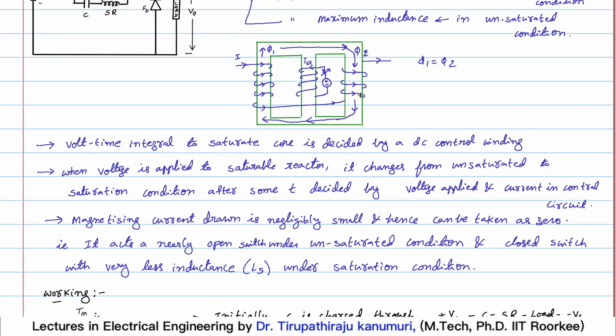The basic characteristic of this saturable reactor is that the voltage-time integral - that is, voltage multiplied by time duration - is fixed and decided by the current passing in the control circuit, mainly the DC control winding. If you apply more voltage, it will go from non-saturation to saturation in less time; if you apply less voltage, it will take more time. The magnetizing current drawn is negligibly small because the control winding already takes care of the flux required.